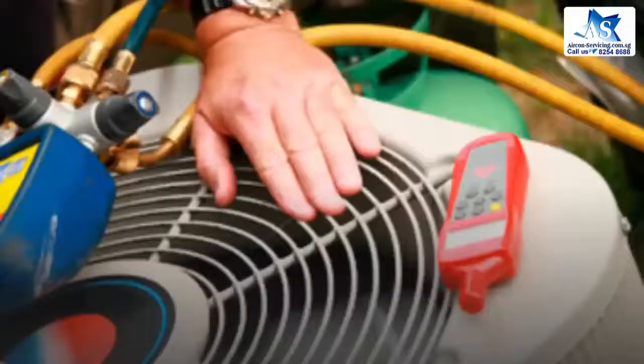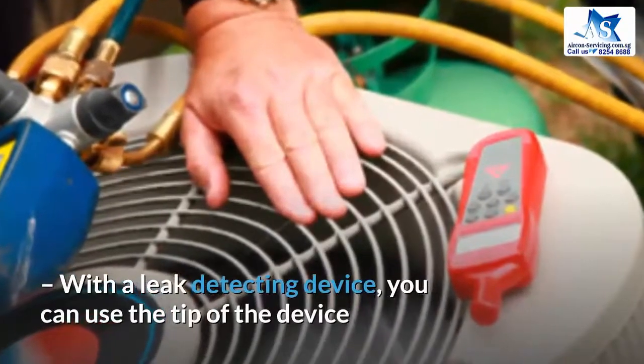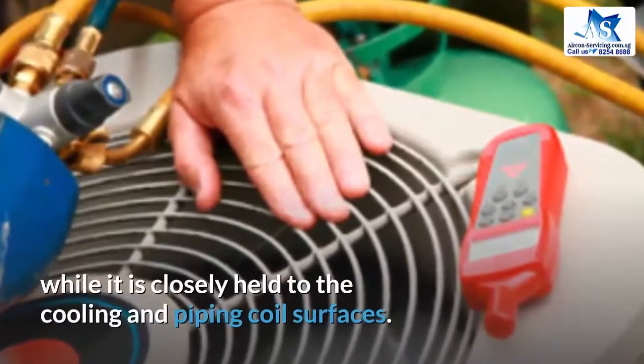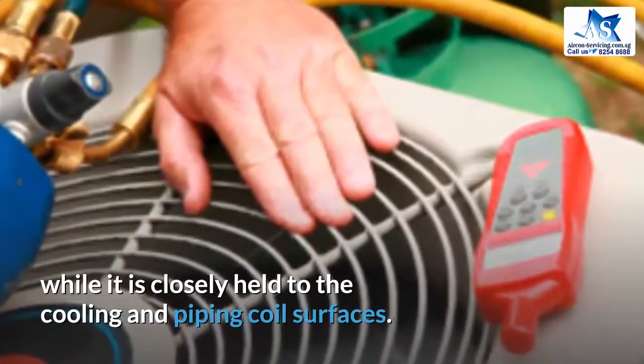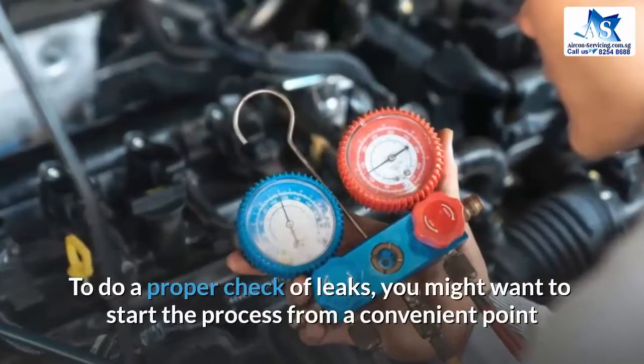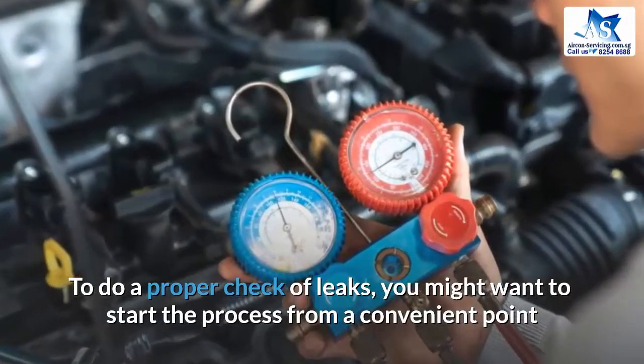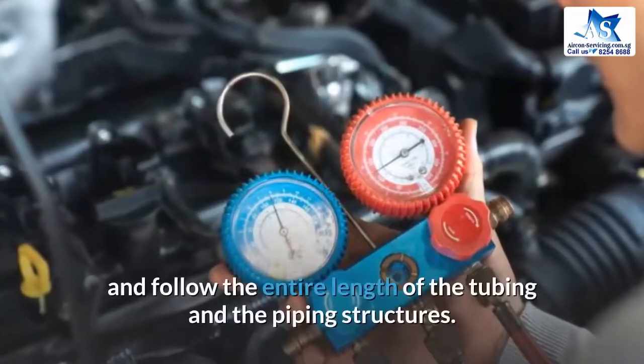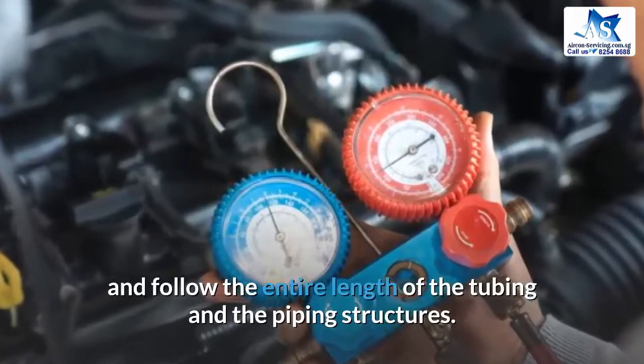If you have a leak detector or any other similar device, you can turn it on and begin using it. With a leak detecting device, you can use the tip of the device while it is closely held to the cooling and piping coil surfaces. To do a proper check of leaks, you might want to start the process from a convenient point and follow the entire length of the tubing and the piping structures.